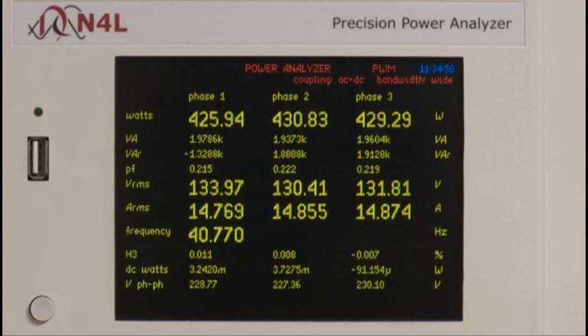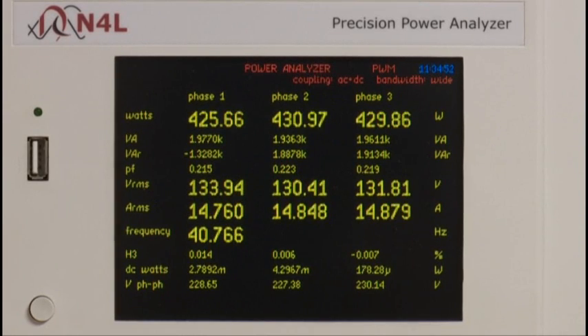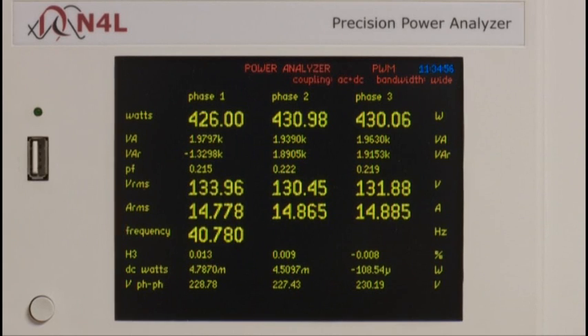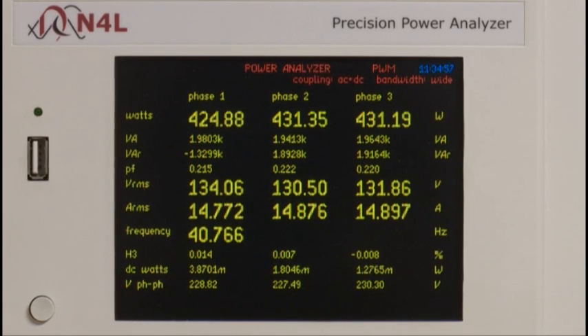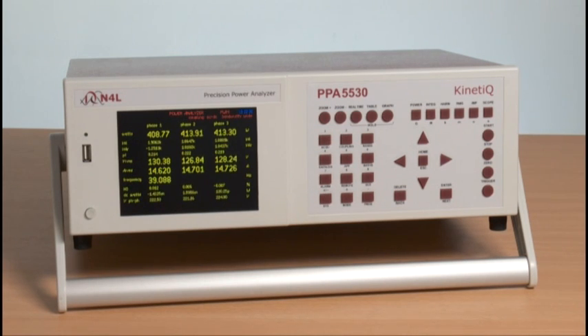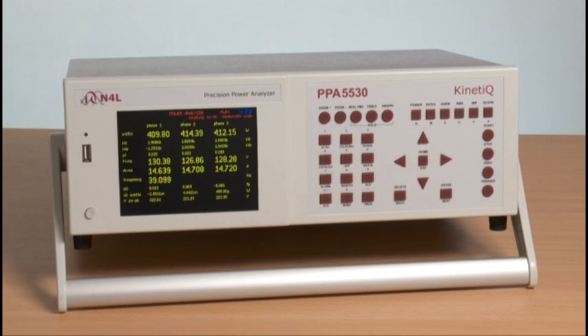Pressing the next key again takes us from the sum values to all three phases displayed simultaneously. Here we can see total power, volts, current and frequency, plus all of the main power parameters, including at the bottom of the display, phase to phase voltage from direct star to delta conversion.